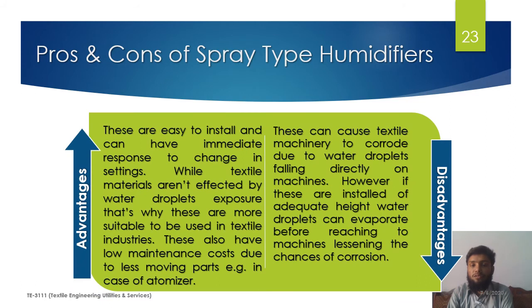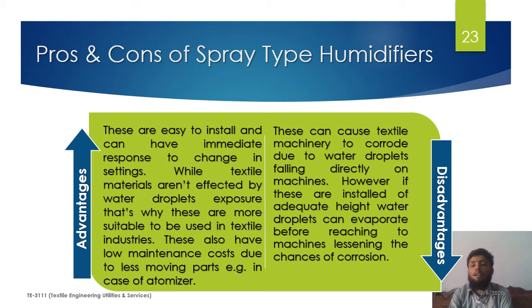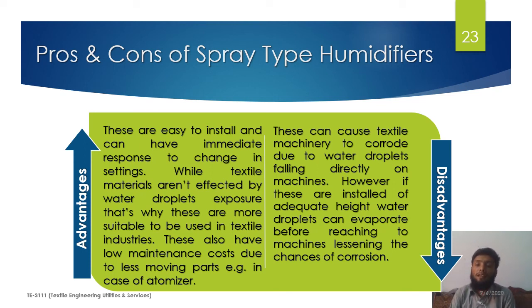Pros and cons of spray type humidifiers: the advantages are that they are easy to install, can change settings immediately, and have very low maintenance and operating costs. A major advantage is that textile materials are not affected by the water droplets, making them very suitable for textile units. The disadvantage is that they can cause corrosion to textile machinery composed of metals. However, if the devices are installed at adequate height, water droplets will convert into water vapor before reaching the machinery, protecting it.